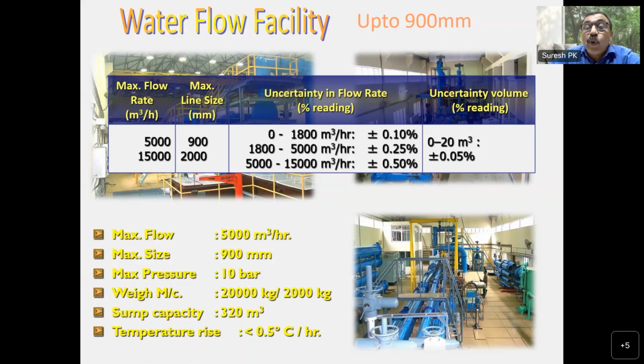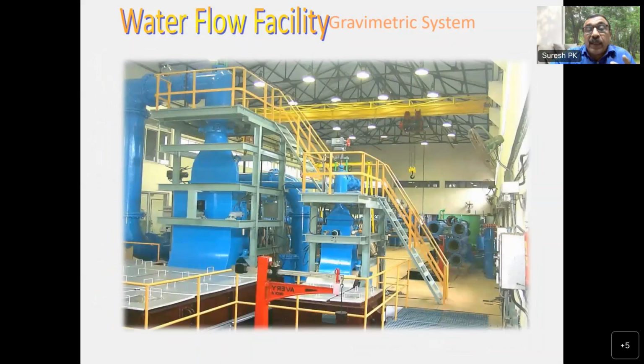So what I have been telling you was, in this system you are using a gravimetric system for measurement, which is supposed to be the most accurate system of flow meter calibration, but it has its own limitations. In this particular water flow lab, they are using the standing start and stop method for the calibration, wherein you measure the volume which is collected or the mass which is collected in a weighing tank for a specified time duration, and then the calibration of the flow meter is done at different flow rates throughout the flow range.